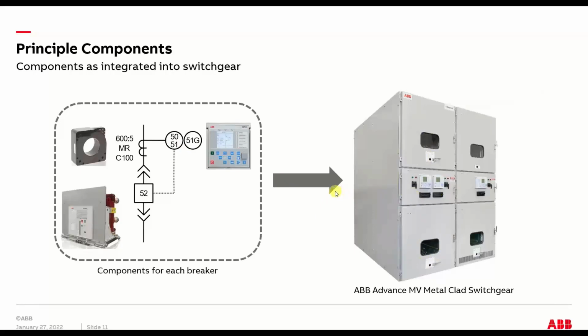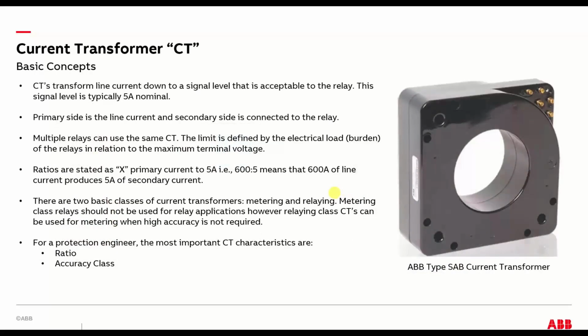bigger system like switchgear. The CT is a big part of designing a protective relaying system, because it really sets the size of the circuit you're going to protect. In the medium voltage world, the first circuit breaker frames, there's not as much variation. So you may have a 600 amp, 1200 amp, 3000 amp frame, and that's it. So you set the current for the specific circuit you're trying to protect based on that CT ratio.